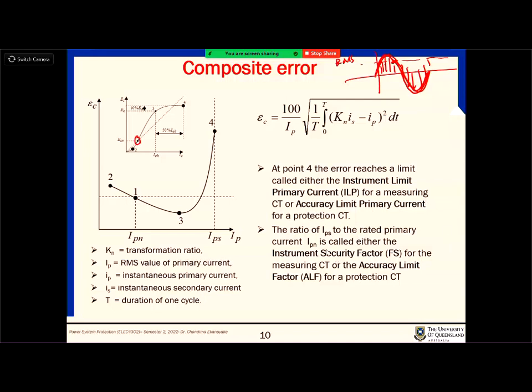So that is how they define it. The ratio of IPS to the rated primary current IPN is called the instrument security factor. So once you find this, IPS is the primary current corresponding to the point 4. Can you see that? Point 4 is the point where you have the accuracy limit level, right? So once you find that IPS, then IPS to the rated primary current, this is the rated point, see? Number 1 is the rated point.